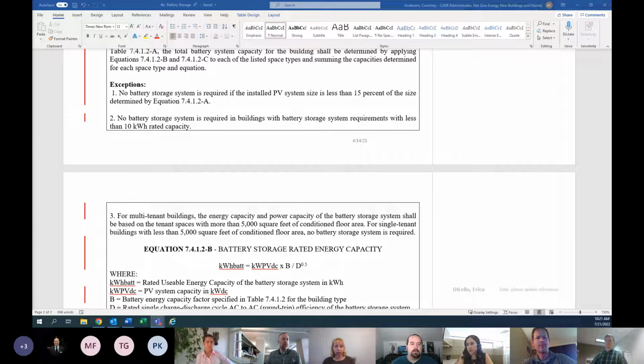So based upon the exceptions, can you help me to understand this? Because I'm confused here. I see a little bit of a conflict. One says you have to have an energy storage, a battery storage system. The other one says you don't. And in my case, the 6,000 square foot building, you have to have 1.5 megawatts. So I'm confused on this.